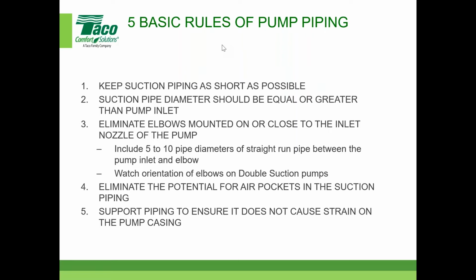Eliminate elbows mounted on or close to the inlet nozzle of the pump. The old saying is 5 to 10 pipe diameters between the pump inlet and an elbow, maybe a long radius elbow. A lot of people nowadays use suction diffusers. That's a piece of equipment that I think every pump manufacturer supplies, and it allows you to have a 90 that mounts right to the suction of the pump. There are straightening vanes in it, so keep that in mind. Watch your orientation of elbows on double suction pumps. You want to make sure that's correct, just to keep the flow going correctly into the pump. Otherwise, you can cause turbulence on that as well.